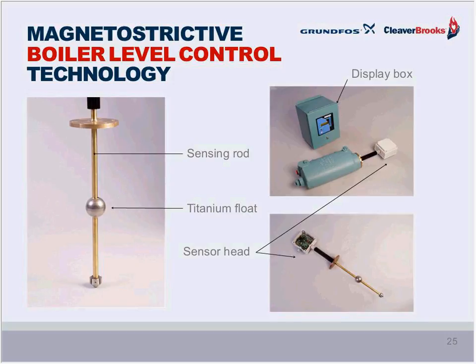But firstly, to accomplish this multifunctionality, you find the sensing rod constructed of red brass and containing an embedded wire, which is constantly and electrically sensing the titanium float as it moves up and down, thereby reflecting the precise water level in the boiler. And then you have the electronics housed in the sensor head, which besides sending the digital and analog signals is also sending the level and alarming signals, both high and low water alarms, to the display box mounted just adjacent to the level control on the boiler.